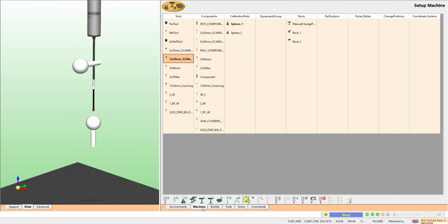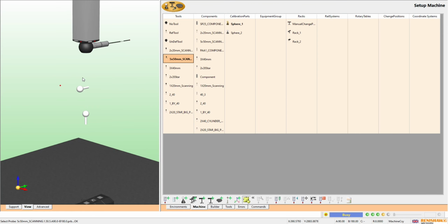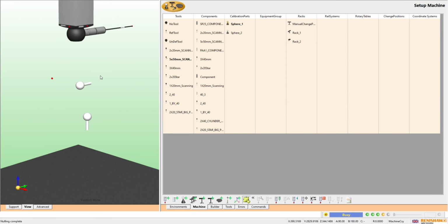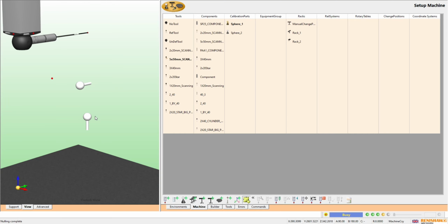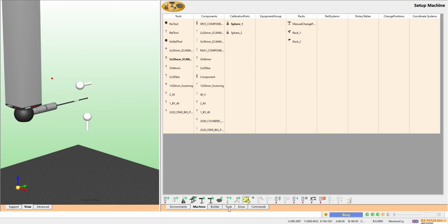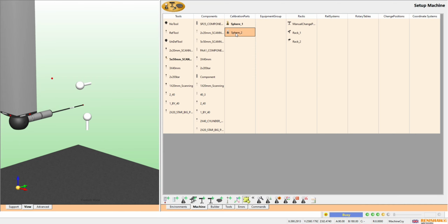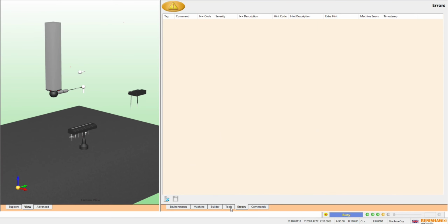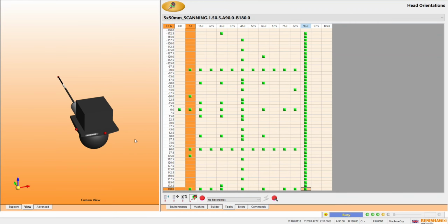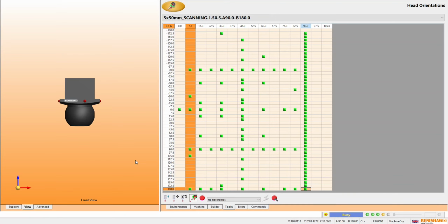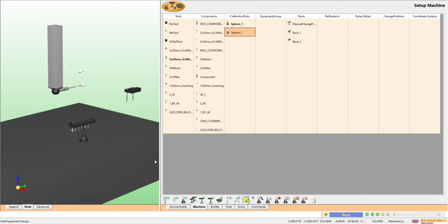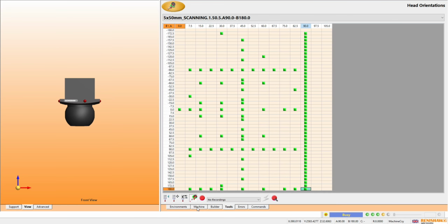So you can see now it moves towards the calibration sphere, and it is going to record. It will calibrate. Calibration is nothing but the actual size of a probe and stylus, which we are cross verifying to see whether it is within tolerance or not, or whether it is capable of inspecting parts on the CMM. That's the simple basic thing. We are using ruby material for the stylus tip.